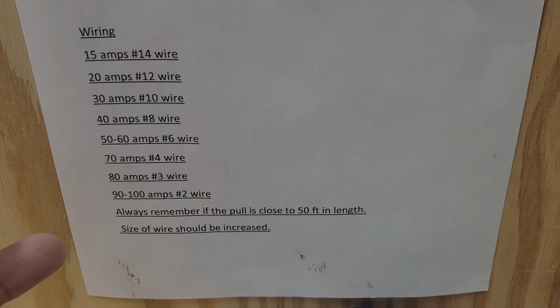That's number three, so we've got a few things that I've told you so far, those are definite things you've got to know. Number four is going to be, you've got to learn wire sizing and amp draw in relation to wire size. So I made myself a little chart here: wiring, 15 amps is number 14 wire, 20 amps is number 12 wire, 30 amps is number 10 wire. I made this for myself as a reminder, and also for the people that work with me, so that they remember the basics.